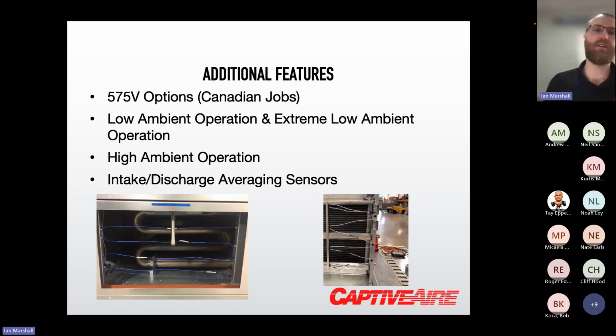Our unit compressor can run into what we call a throttling state, which essentially ramps down the compressor speed to prevent us from going out on a high head pressure on those really, really hot days. The high ambient option is a physical hardware option: we use a beefed up, higher output condensing fan and a slightly lower factory charge. That prevents the unit from going into this throttling condition, so we don't ramp down the compressor at peak heating or peak cooling conditions. It's case by case, based off the weather design data of a given location. If we're looking at an area with a 105 to 110 ambient design, that could be something to consider. Intake and discharge averaging sensors, as I think I mentioned before.